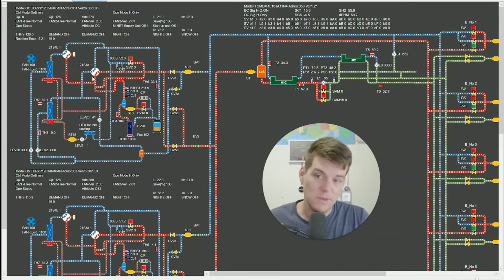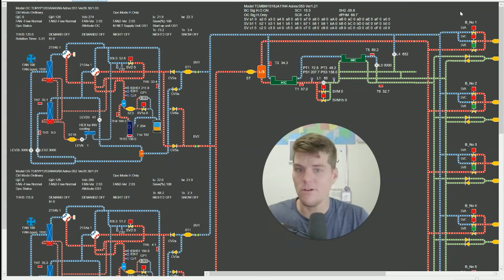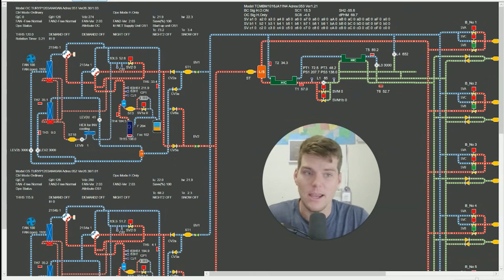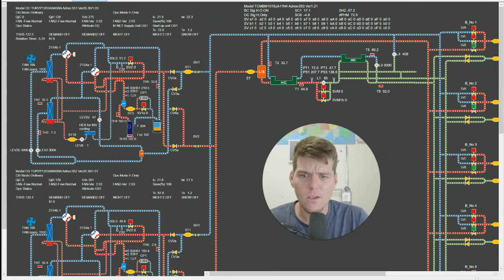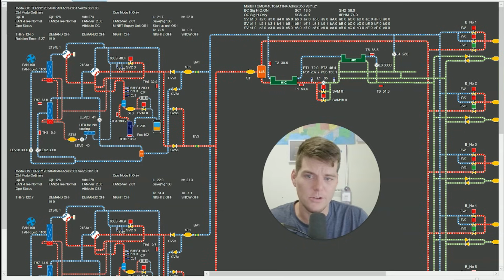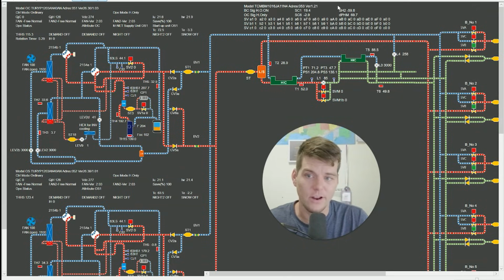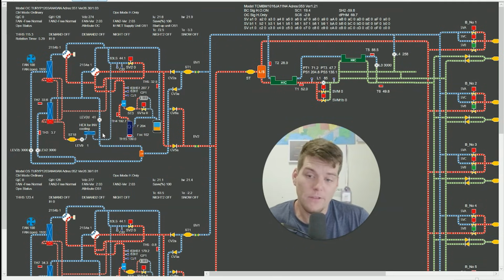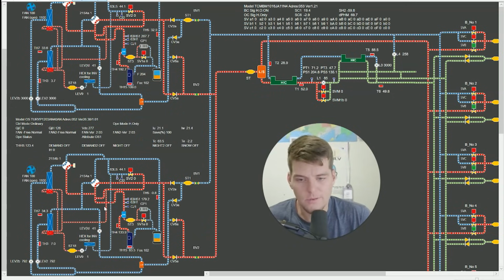because none of these sensors are changing, and these designations may be foreign to you if you've never looked at this. Maybe you're very familiar with Mitsubishi, and it's just foreign to me. But at the top right-hand side here, I can actually scroll through the data points on how this system is operating and watch these temperatures as they change. It is set to Fahrenheit right now. And so this top left unit is my master unit, and this bottom left unit is my subunit.